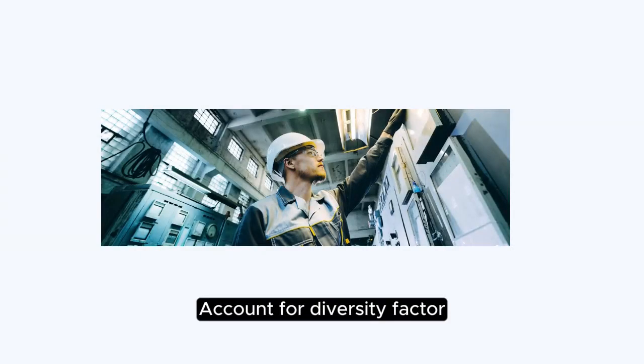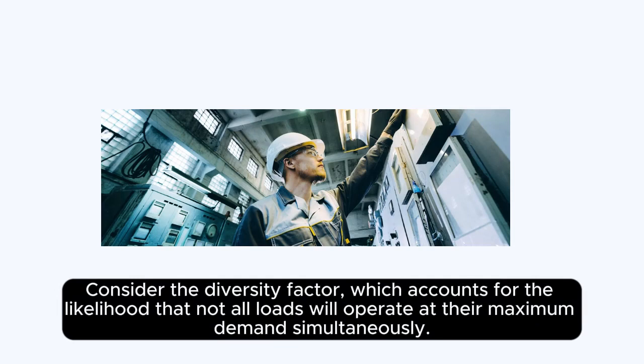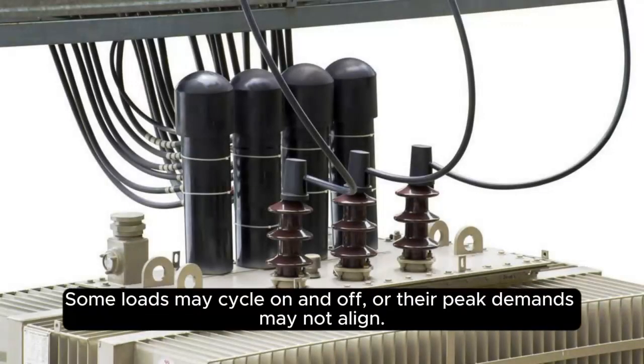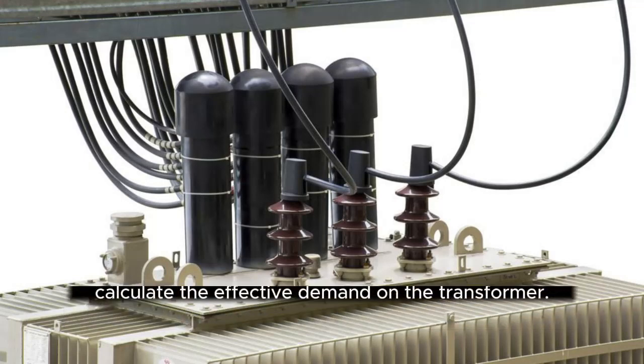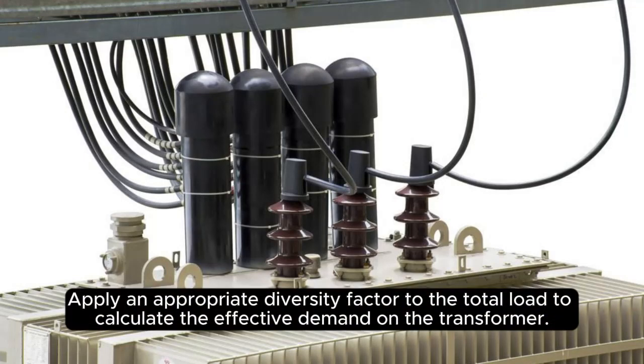Account for diversity factor. Consider the diversity factor, which accounts for the likelihood that not all loads will operate at their maximum demand simultaneously. Some loads may cycle on and off, or their peak demands may not align. Apply an appropriate diversity factor to the total load to calculate the effective demand on the transformer.